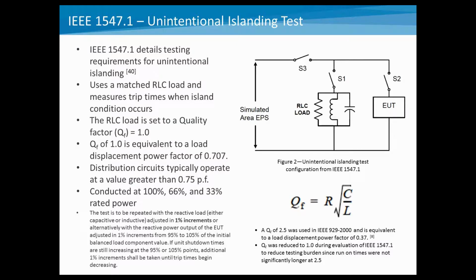So in the diagram you see EUT, that stands for equipment under test, and then that's connected to a load bank. In this case it's an RLC load that basically matches real and reactive power. And to conduct the test, you match the RLC load bank with the output of the device under test until you have basically no current flowing through that switch S3. At that point, you can open that switch and see how long you can maintain that island between the load bank and the equipment under test.